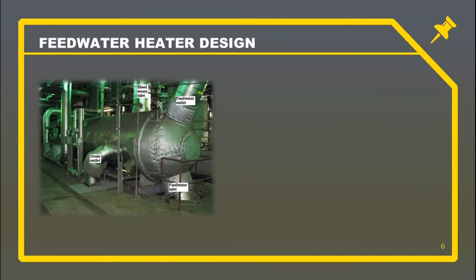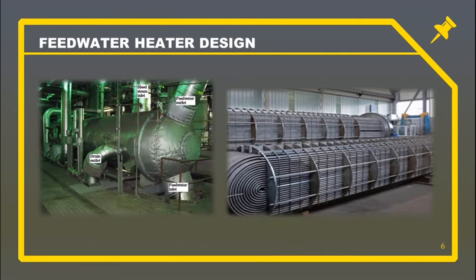Feedwater heater design. Most feedwater heaters are shell and tube design, in which a bundle of tube stack is contained within the outer shell. U-tubes are the most common tube bundle configuration as they are relatively resistant to thermal expansion during operation.